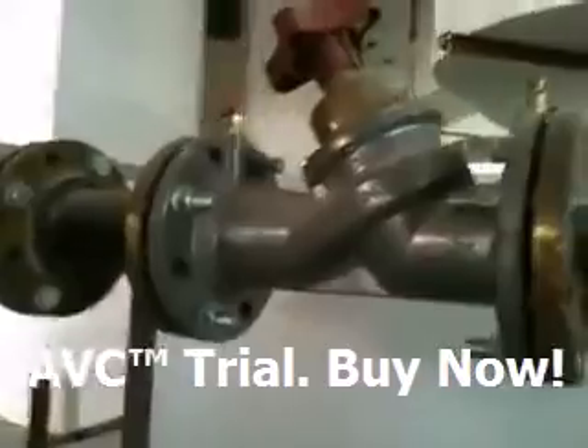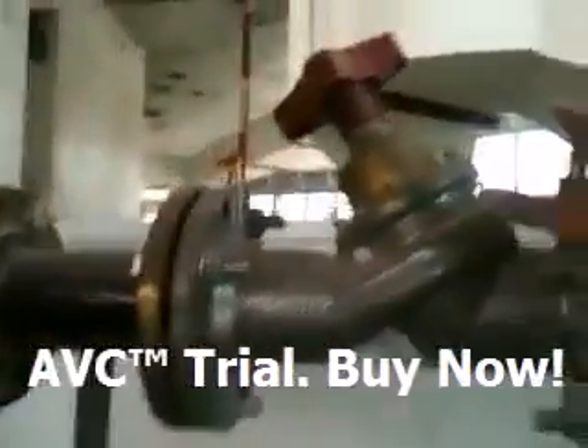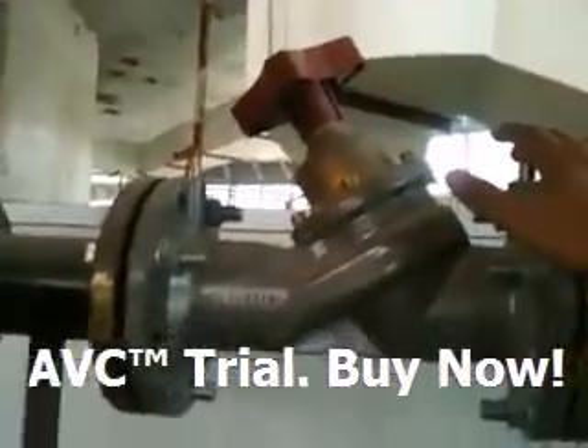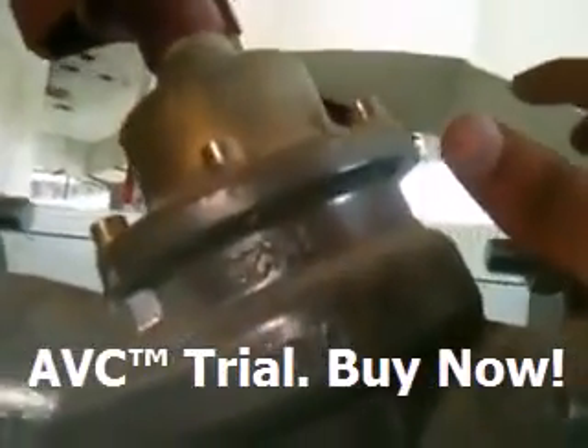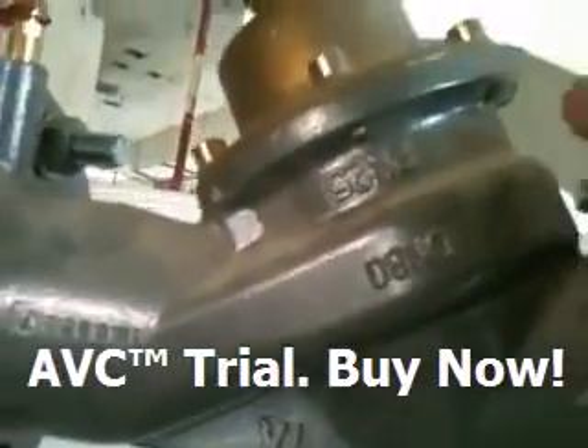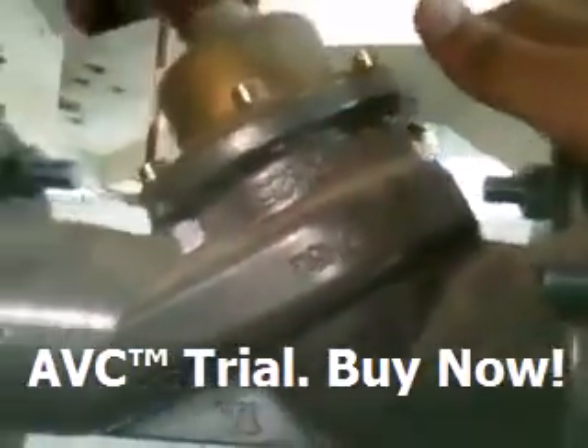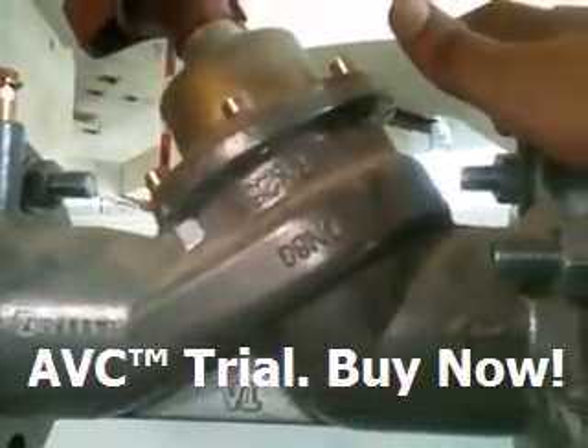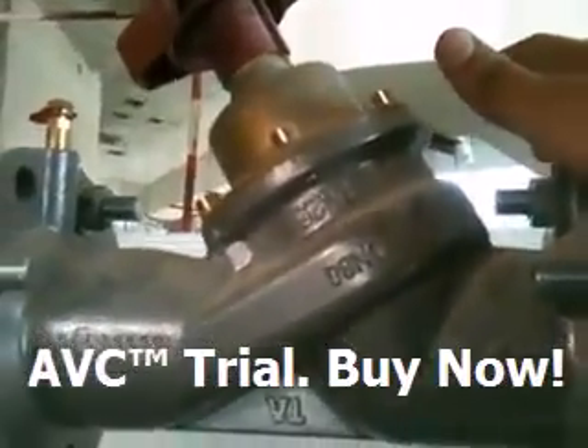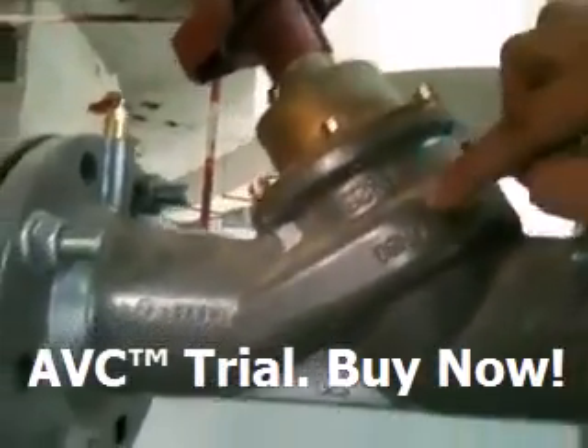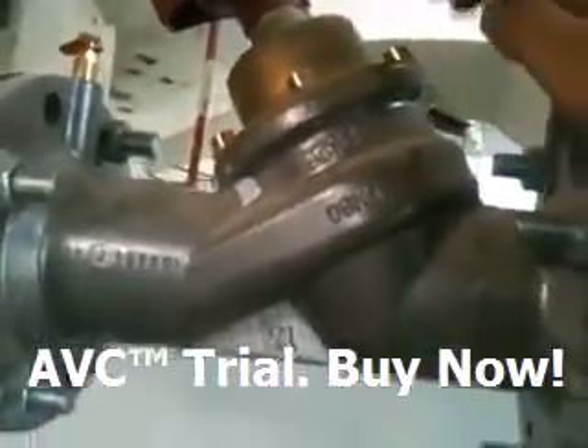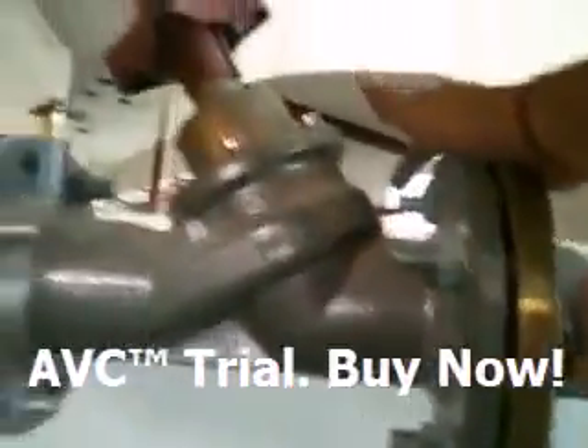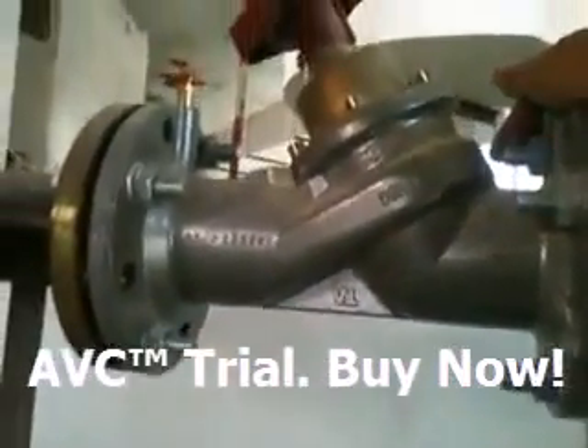This is known as DRV, that is double regulating valve. This also has a rating of PN25, meaning its flanges can withstand line pressure of almost 25 bar. This DN80 means it has a 3 inch diameter, or 80 mm.